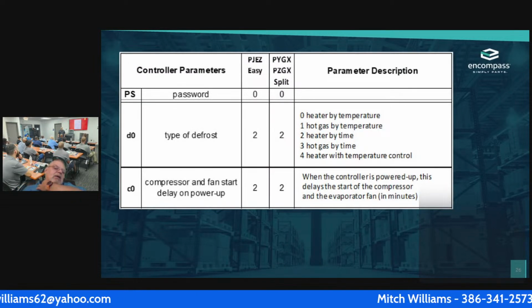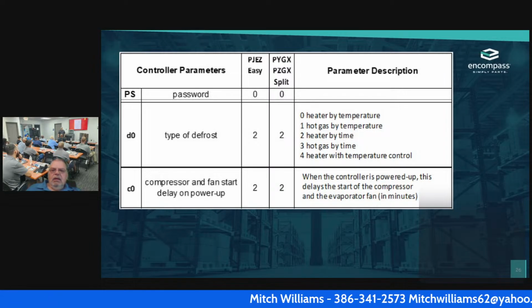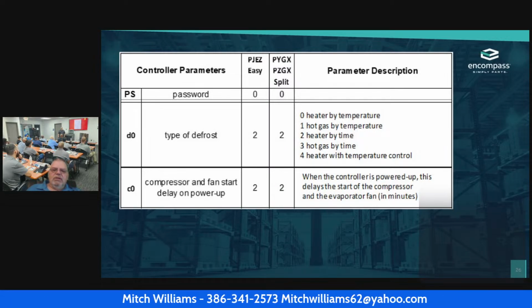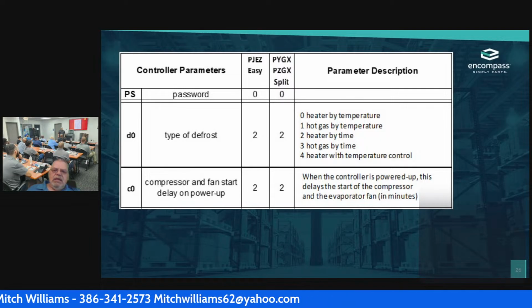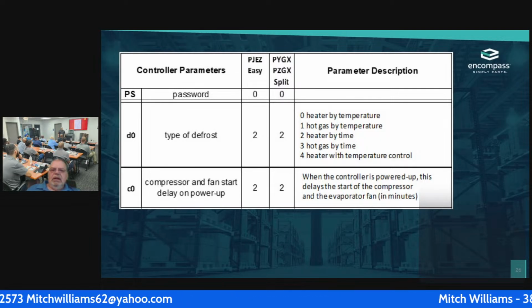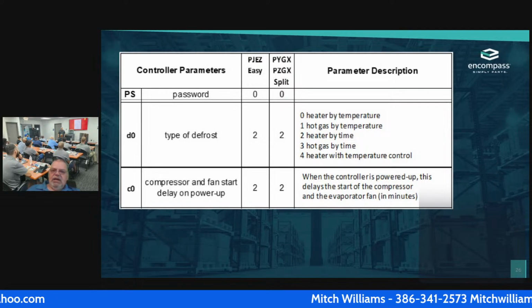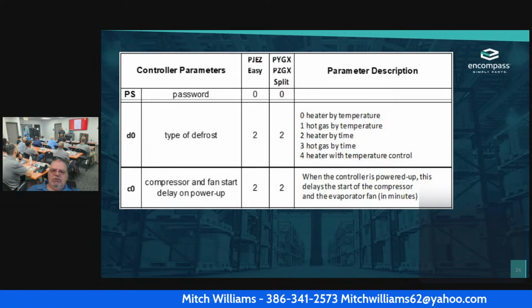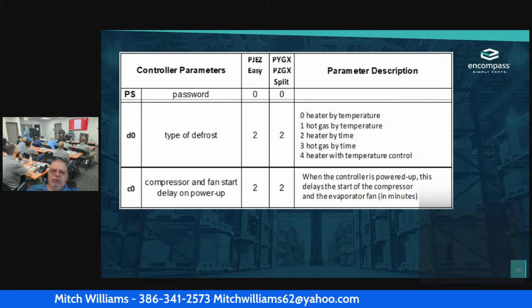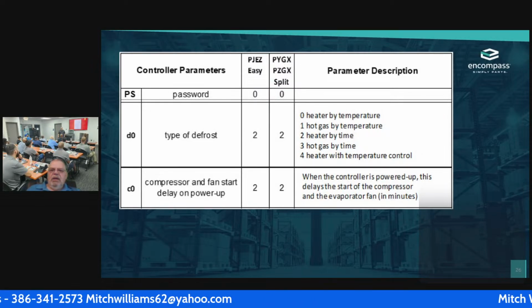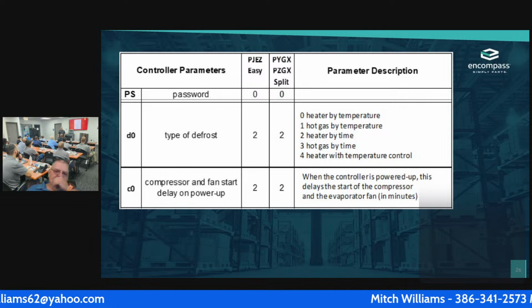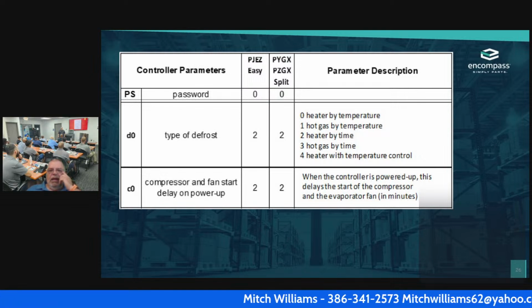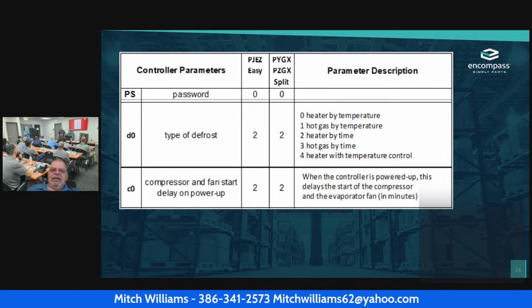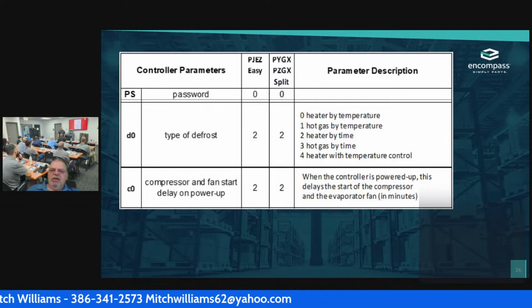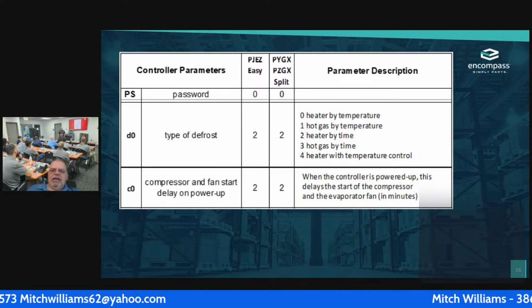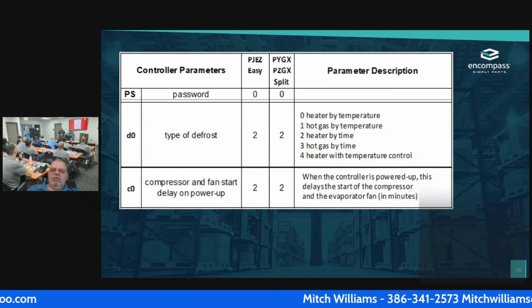Okay. If I have a d0, okay, DO is the defrost. What is it? On the PJEZ, it's set for 2. If I go to the PYGX or the GX, that's set for 2. What does that mean? The heater is on by time. If I turn it to 0, that tells me that I go by temperature. 1 is the hot gas by temperature. 2 is the heater by time. 3 is hot gas by time.